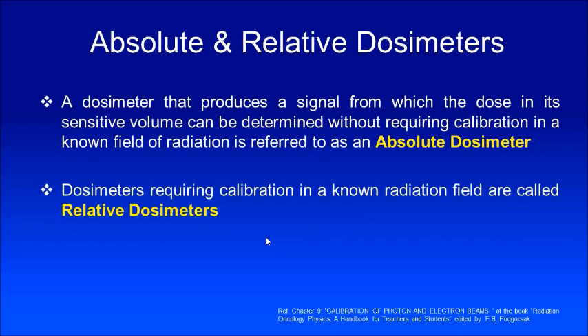What are absolute and relative dosimeters? A dosimeter is said to be an absolute dosimeter if it produces a signal from which the dose in its sensitive volume can be determined without requiring a calibration in a known field of radiation. So an absolute dosimeter should not require a calibration — it should directly give you absorbed dose. Calorimetry, Fricke, and free-air ionization chambers could be referred to as absolute dosimeters.